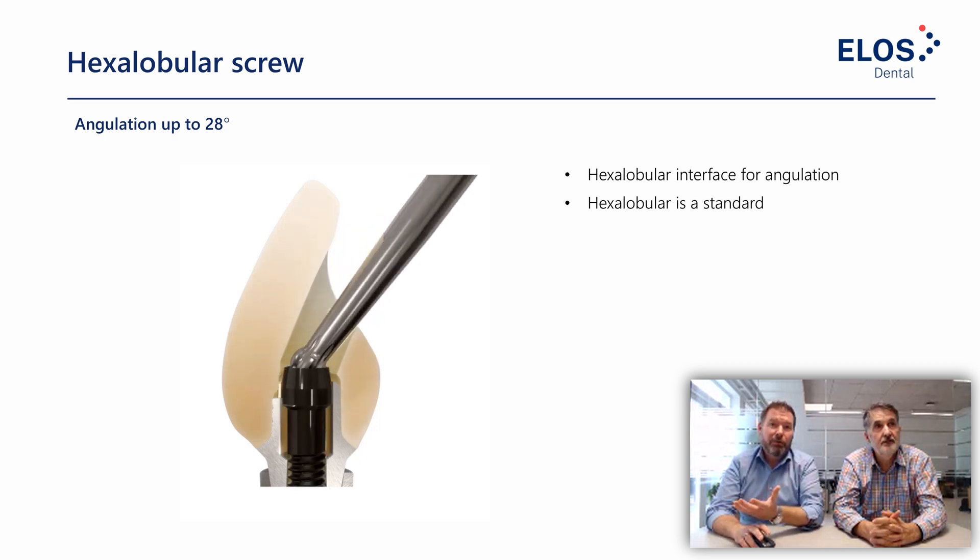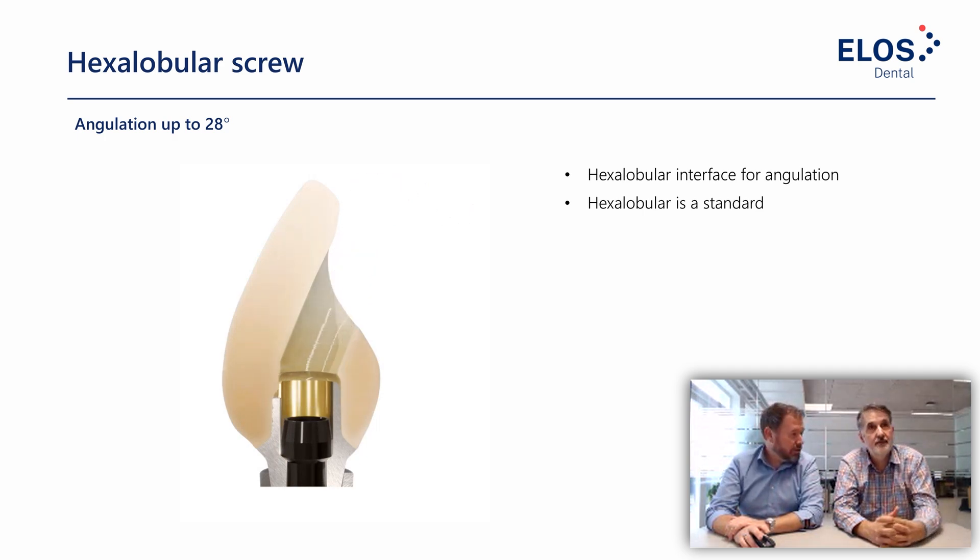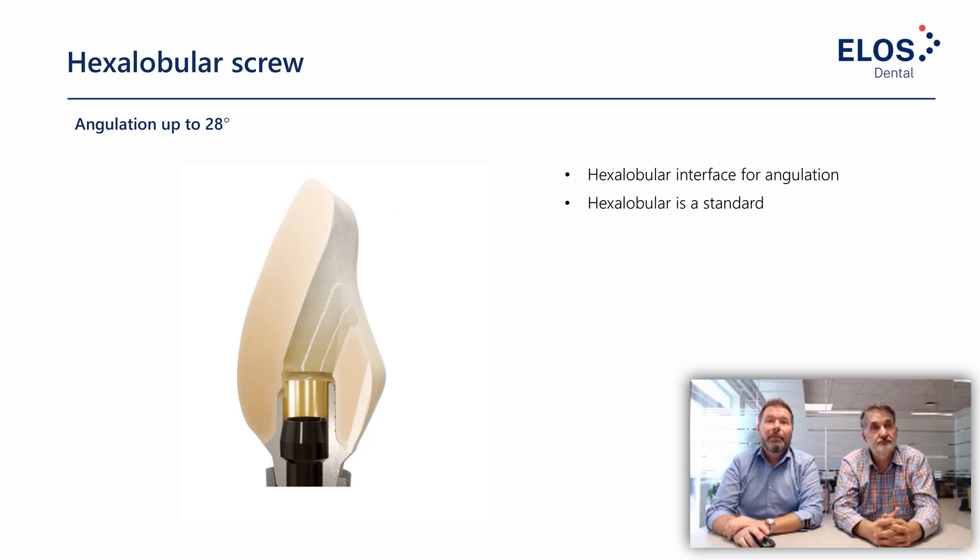The hexalobular screw allows for angulation of the screw channel, which is important for aesthetic reasons. The hexalobular design is a standard used by many manufacturers — it allows angulation up to 28 degrees. On the driver side, we have slightly improved the dimensions so we can achieve a slightly higher torque on the driver, but it's still a standard compatible with basically all hexalobular drivers.